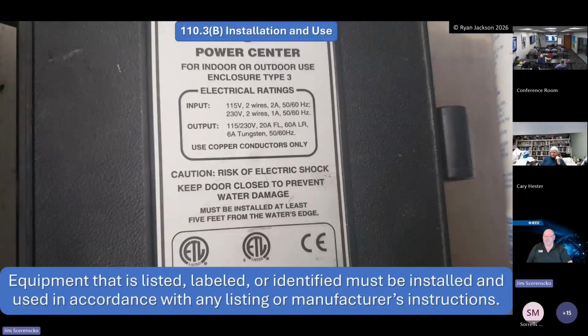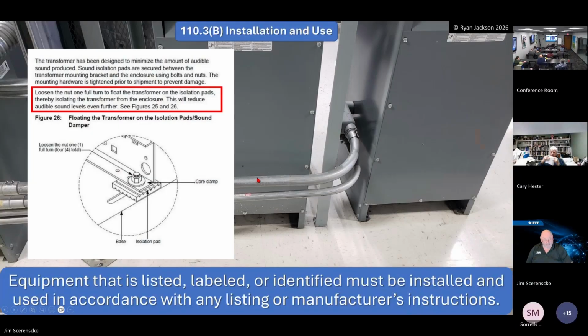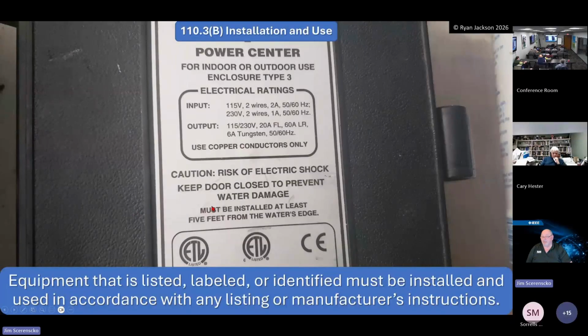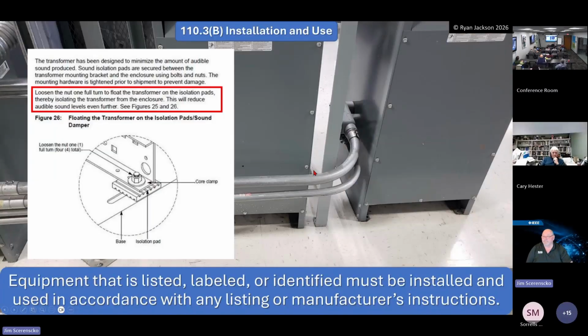Equipment that is listed and labeled must be installed and used in accordance with any of the listing or manufacturer's instructions. That's 110.3(B). That's what we fall back on as inspectors a lot. It's interesting that it says water damage. Risk of electrical shock, keep the door closed to prevent water damage. Must be installed at least 5 feet from the water's edge. And then, of course, the installation and use gives you the information on the installation guide, which is probably inside the transformer, which nobody looks at.